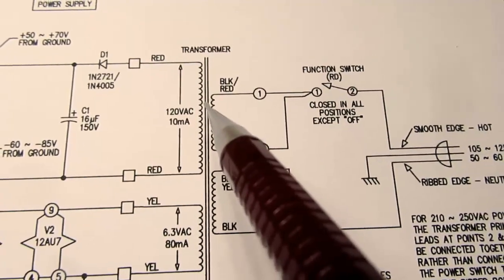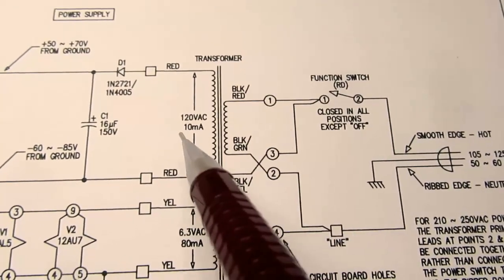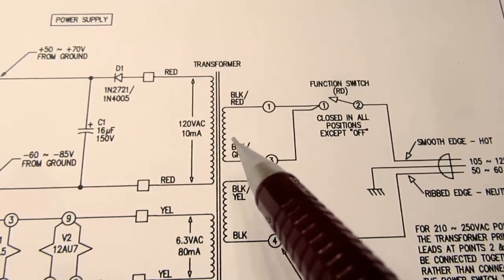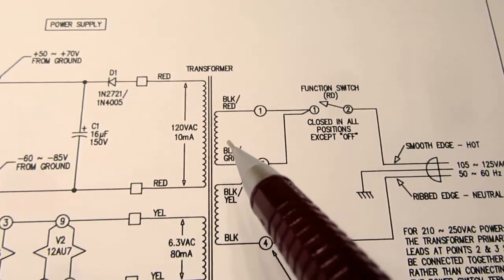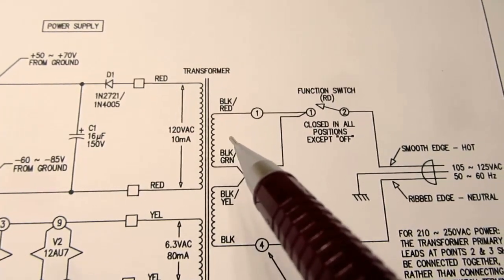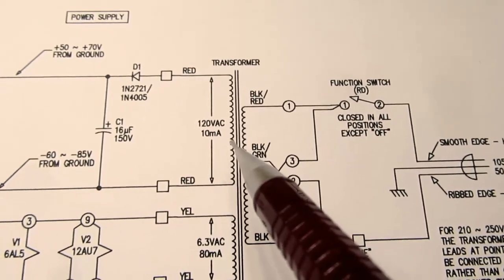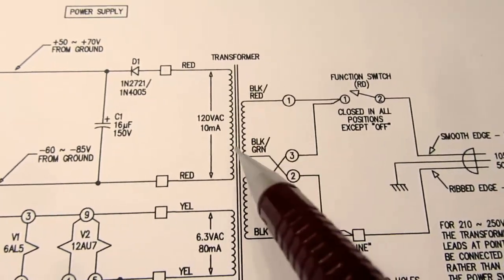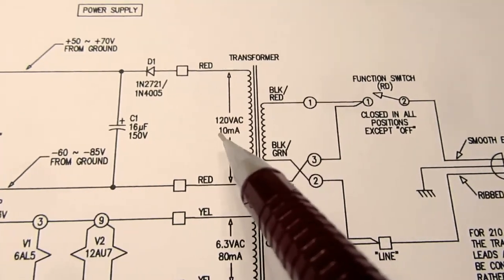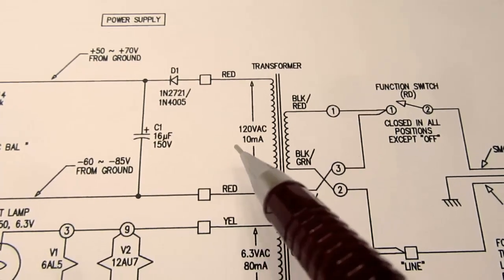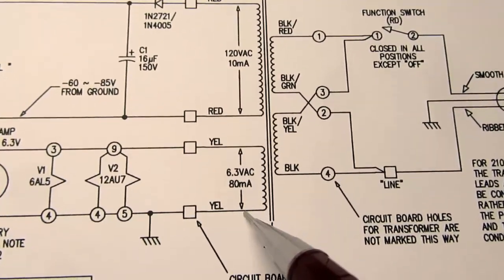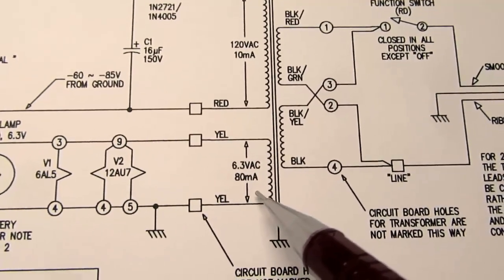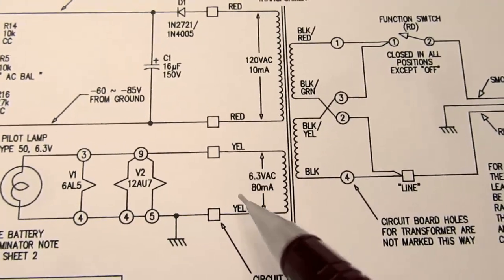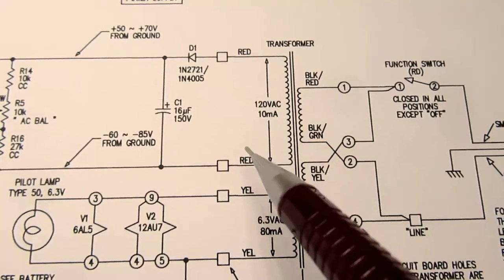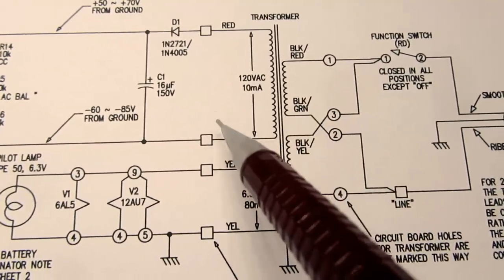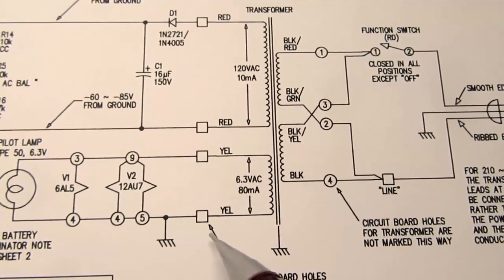I mentioned it earlier that this transformer is for the most part just a 120 volt to 120 volt isolation transformer that gives the meter, for most situations anyway, electrical isolation from the line voltage. But it's not a step down. So we have this 120 volt winding here. It's only rated for 10 milliamps, but the high impedance circuit it's running doesn't require very much. We also have another secondary winding. This is for the filaments of the tubes. It's 6.3 volts, rated for 80 milliamps. And that has yellow wires where the principal secondary winding has red connections. And all those secondary wires terminate to unmarked holes on the printed circuit board.